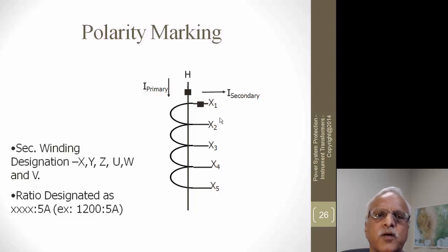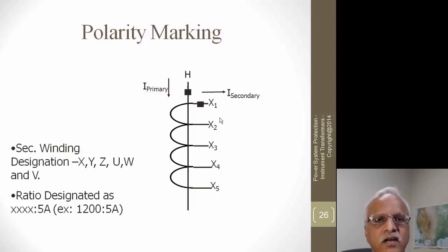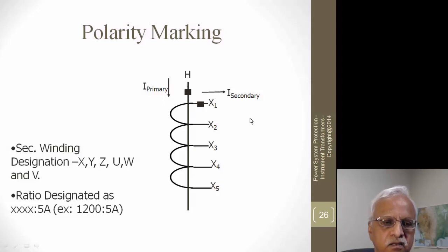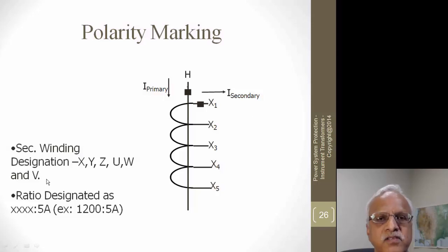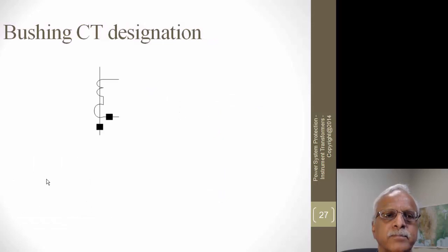Polarity marking is very important, especially for directional relays or bus protection where the sum of all currents must equal zero. The convention is: when current enters the polarity marking on the primary side, it leaves the polarity marking on the secondary side. Different designation numbers — H and X — are used, and for multiple CTs they are designated X, Y, Z, and W. In freestanding CTs with five or six cores, this labeling is used. Bushing CTs are also designated with the H marking as shown in the drawings.